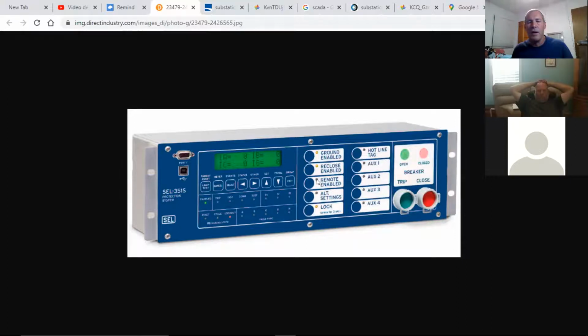Turn it off, then hit the hotline tag. Remember, the only thing I can do when it's in remote, SCADA controlled, is trip it open. You've got to take local control. So you press this button, the light turns off, then do the hotline tag. Press that button, you'll get a light here and it'll show in the window.